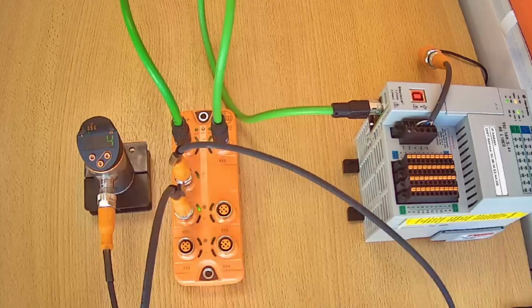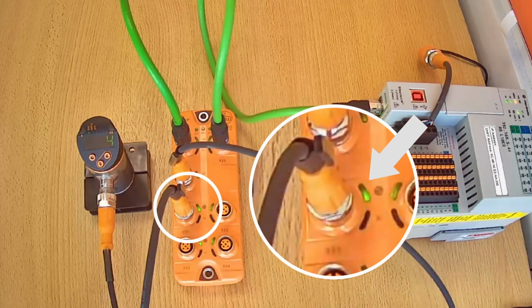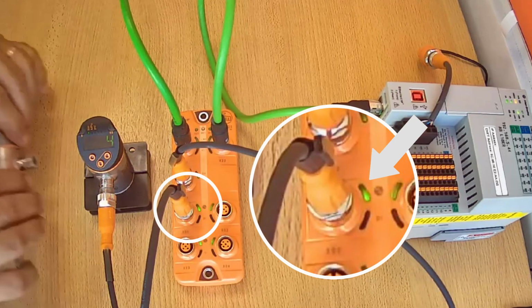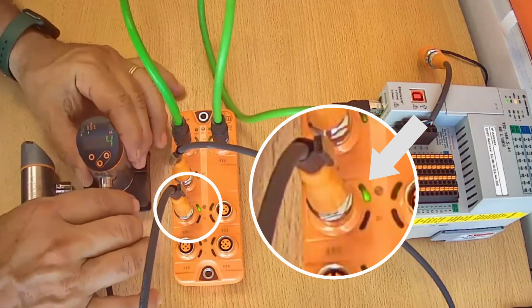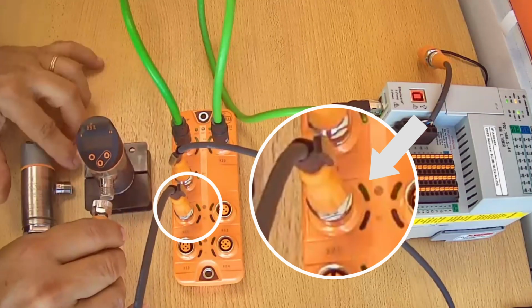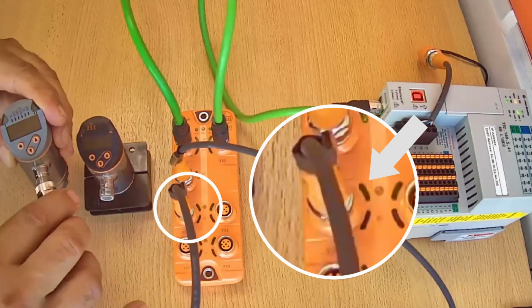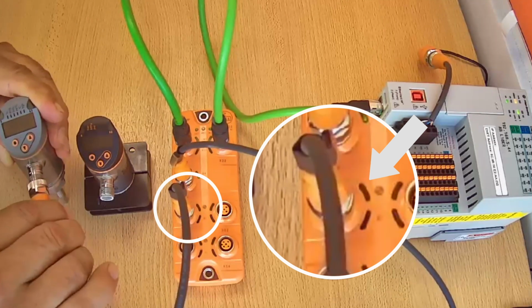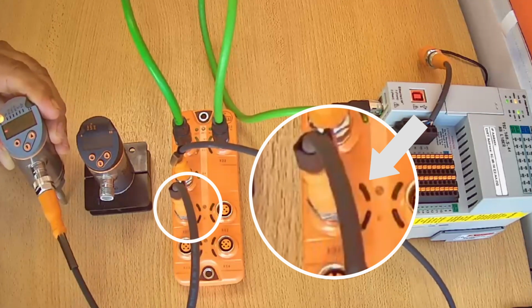First, we check the master's device validation. If the correct sensor is connected, as shown here, the corresponding status LED will be solid green. Now we unplug the M12 connector, the port detects that no sensor is being read, and we can see the green light flashing. Now we plug in another sensor.